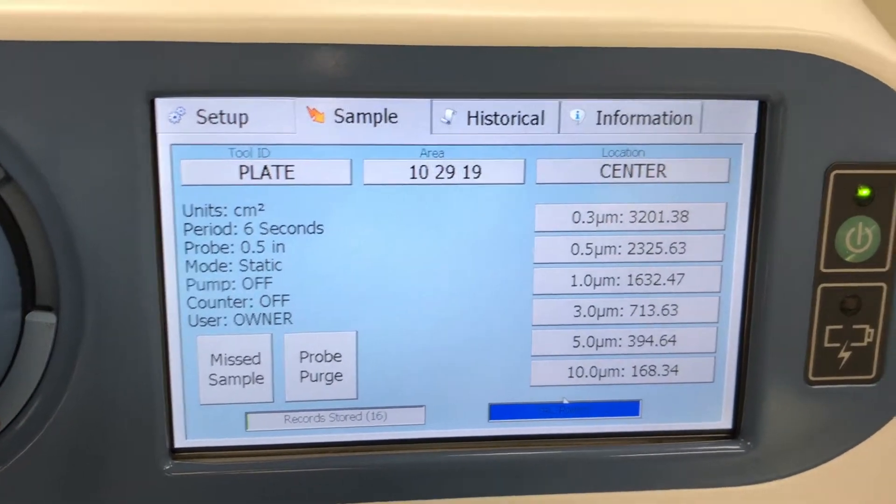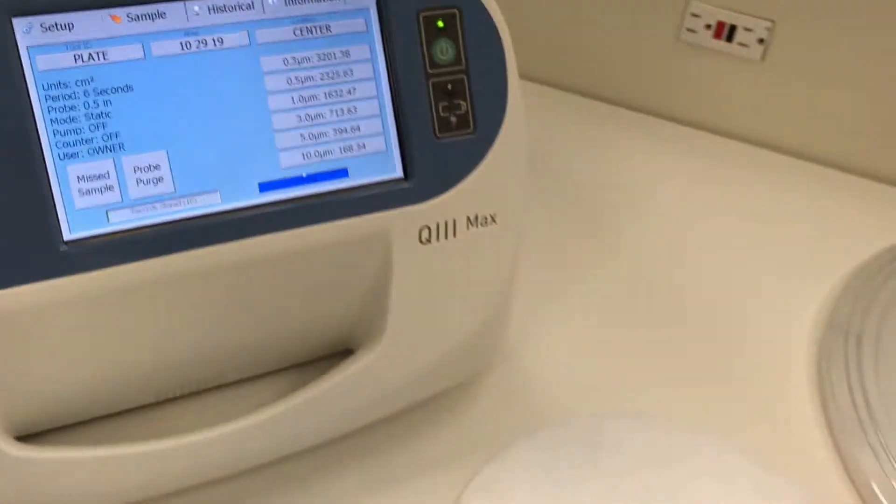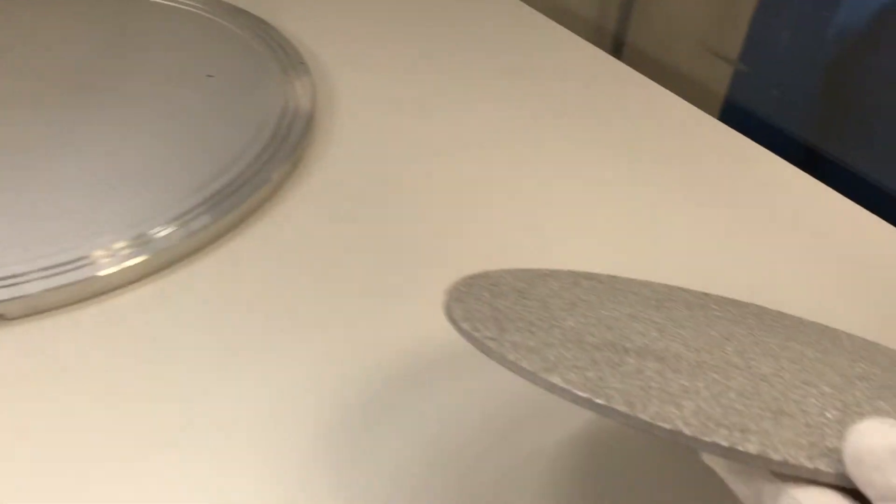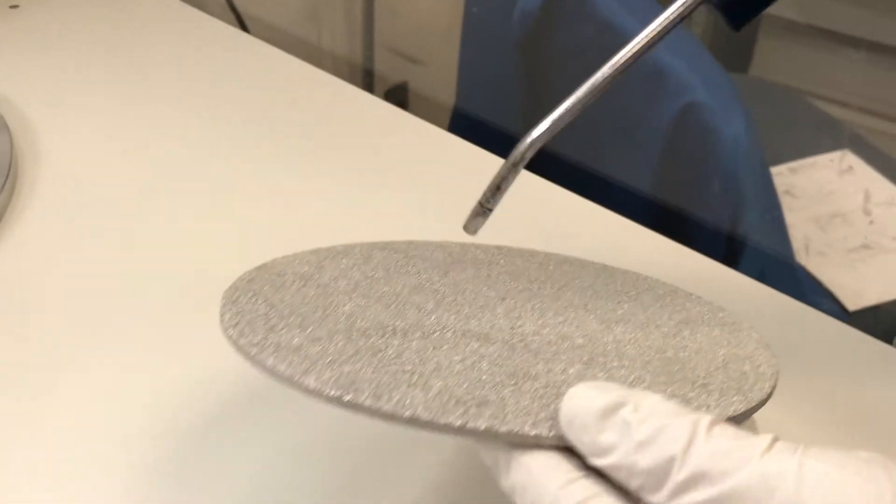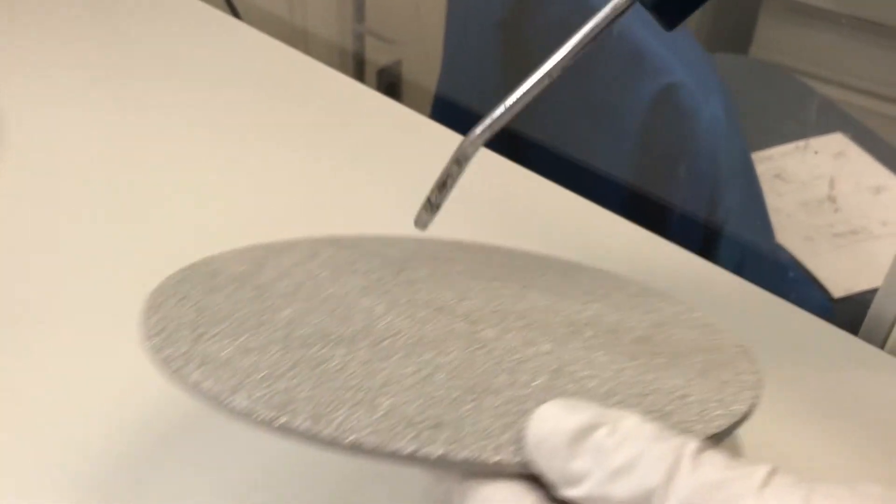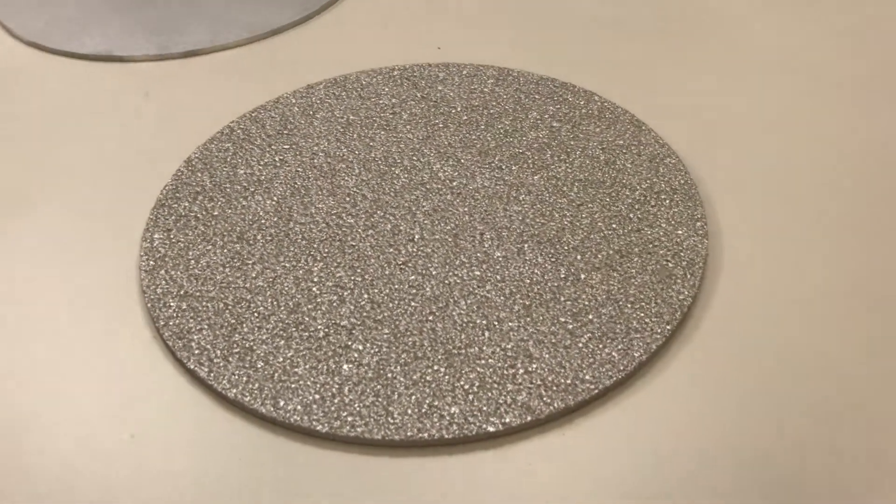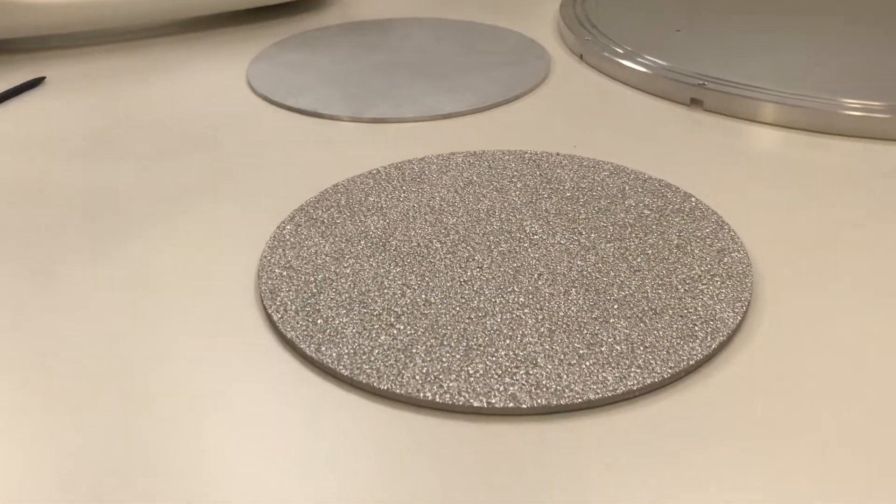Because this plate is so contaminated and rough, it can't be wiped with the wiper and IPA. And we are cleaning it using nitrogen to blow off the surface. Nitrogen or clean dry air is quite effective in removing particles lightly adhered to the surface.